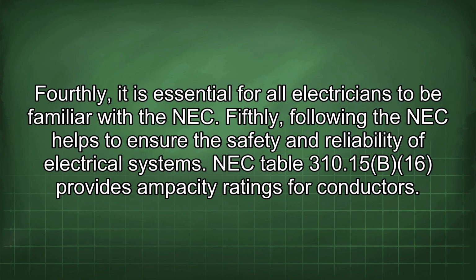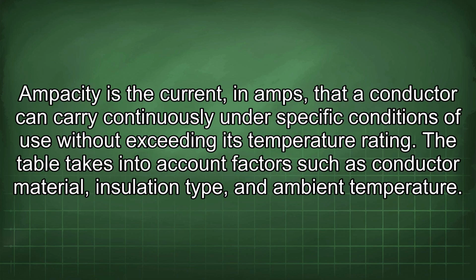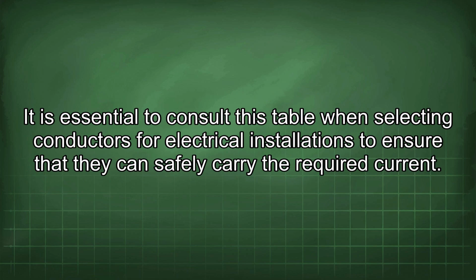NEC Table 310.15(B)(16) provides ampacity ratings for conductors. Ampacity is the current, in amps, that a conductor can carry continuously under specific conditions of use without exceeding its temperature rating. The table takes into account factors such as conductor material, insulation type, and ambient temperature. It is essential to consult this table when selecting conductors for electrical installations to ensure that they can safely carry the required current.